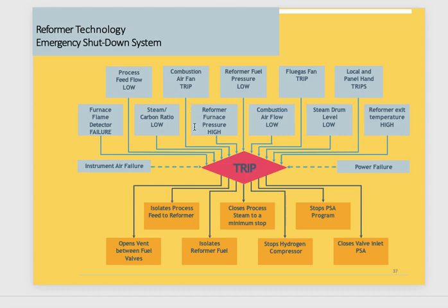Okay, and as a surprise to you, in the negative also, in the deep negative, if this reformer is exposed to a huge vacuum, it will trip also, like minus 70 millimeter H2O with 0 second or minus 30 with delay time. Okay, you understand?